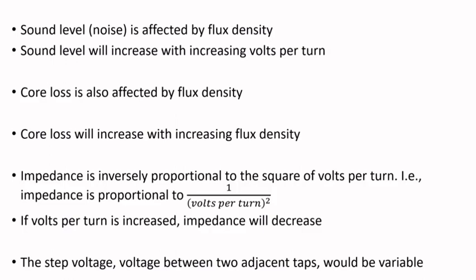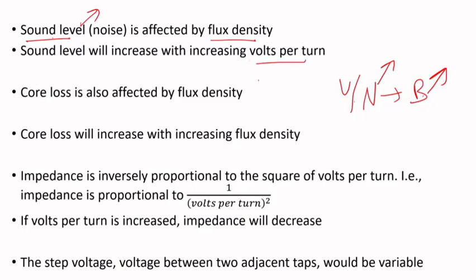Sound level and noise are also affected by flux density. Since volts per turn is changing, flux density depends on it — if volts per turn goes up, flux density goes up, and noise increases. Core loss is similarly affected by flux density: if volts per turn increases, flux density increases, and core loss increases as well.